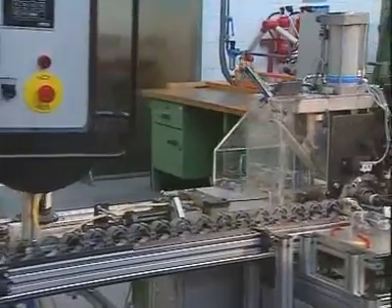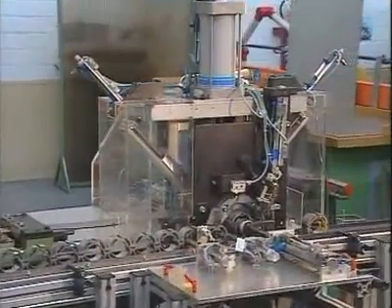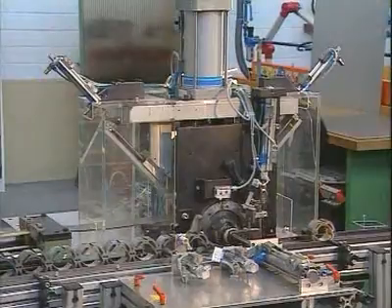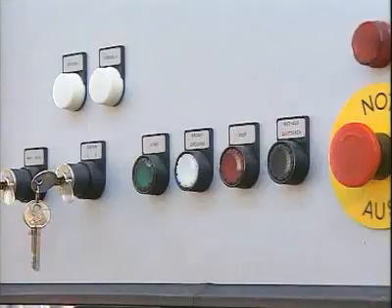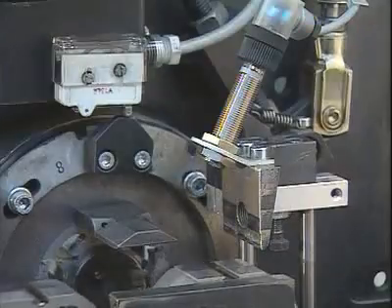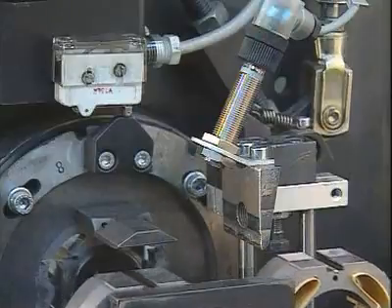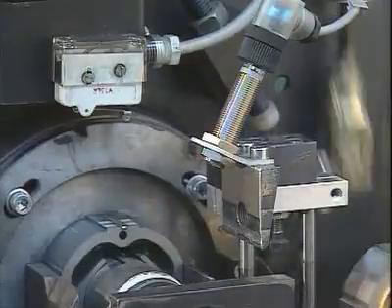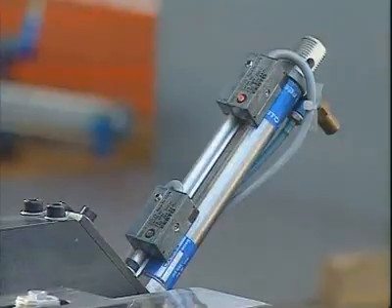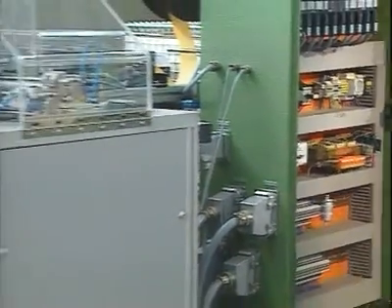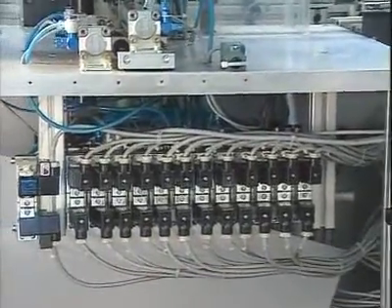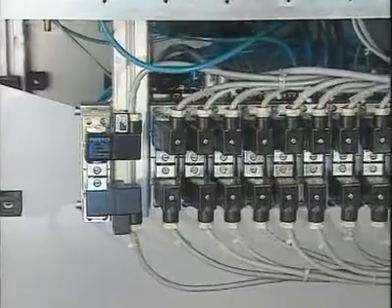Now let's take a look at what happens in practice. The elements of the control part are of course distributed throughout the entire system. The signal elements, here the push buttons for operation, the sensors, and the solenoid switches on the pneumatic cylinders send electrical signals to the machine controller. From there, the solenoid valves are controlled. So here we have the interface between the electrical signal part and the pneumatic control part.